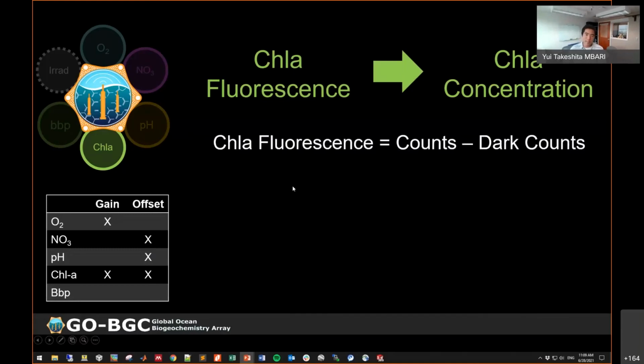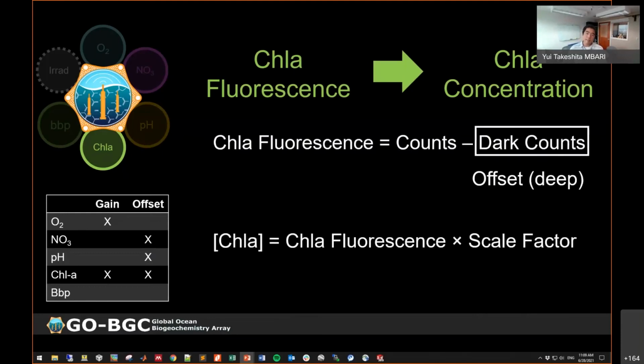The fluorescence is the counts from the sensor minus the dark counts, which is essentially what the reading is when there's no chlorophyll present. This represents the offset adjustment that's applied to the sensor, and we can calculate what this offset is based on deep measurements where there's no chlorophyll available.